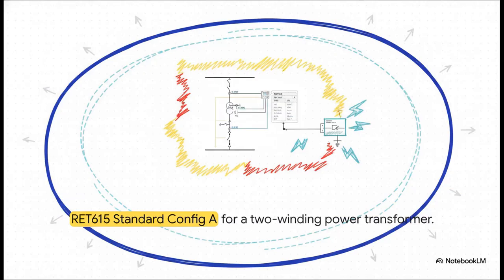To make this work in the real world for a standard two-winding power transformer, current transformers, or CTs, are installed on both the high-voltage and low-voltage sides. They feed their data directly back into the relay. This creates a very strictly defined zone of protection. If absolutely anything goes wrong inside that specific zone, right between those sensors, it is the relay's responsibility to catch it and clear it immediately.